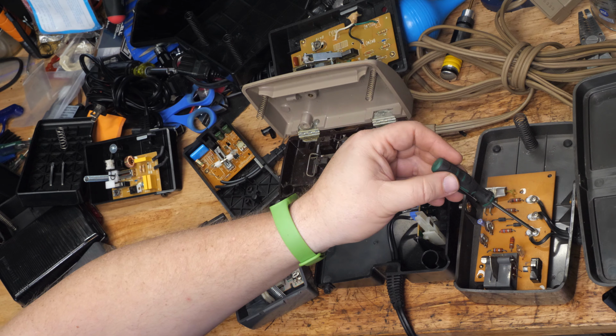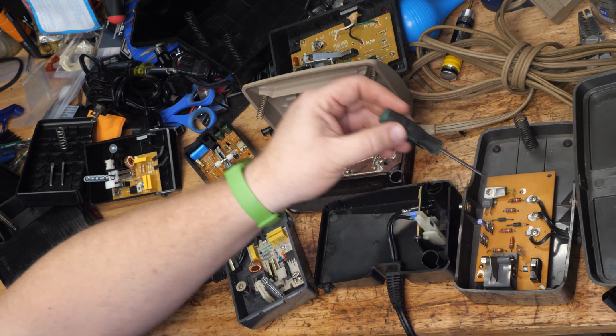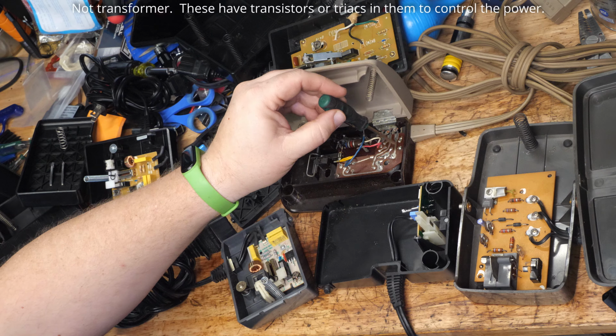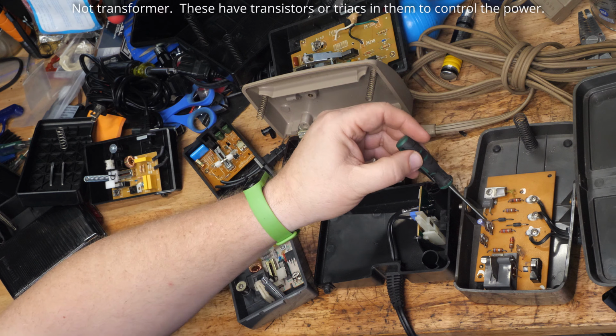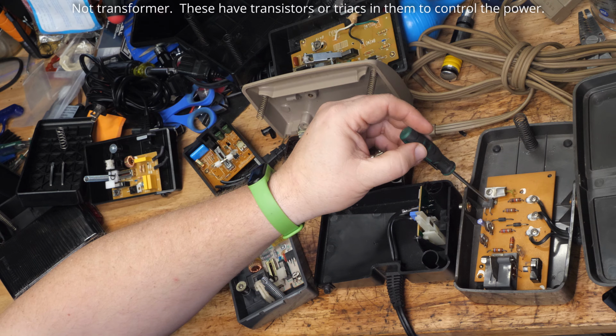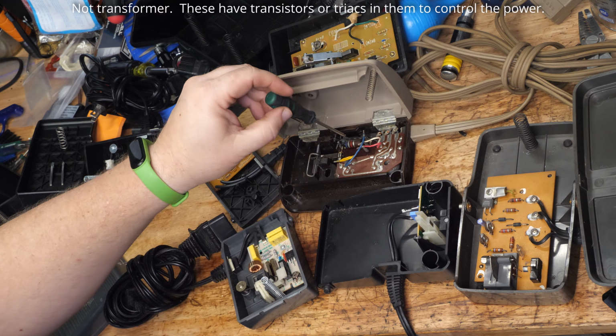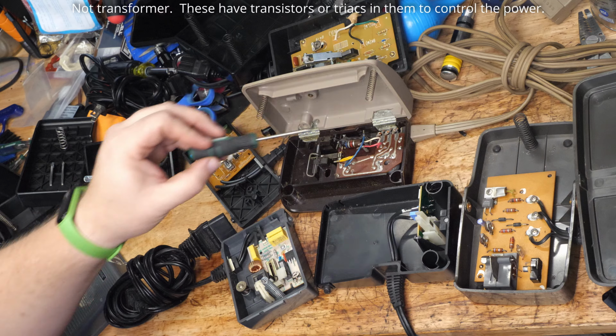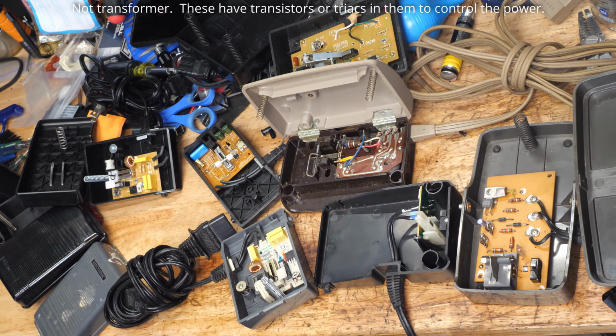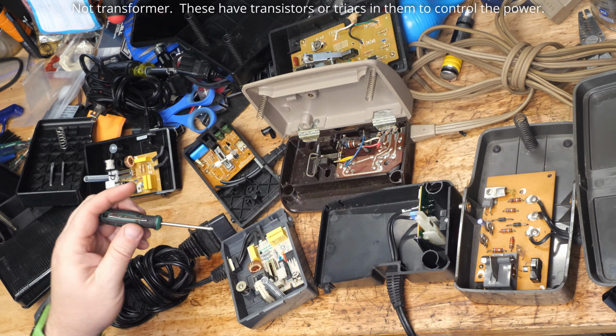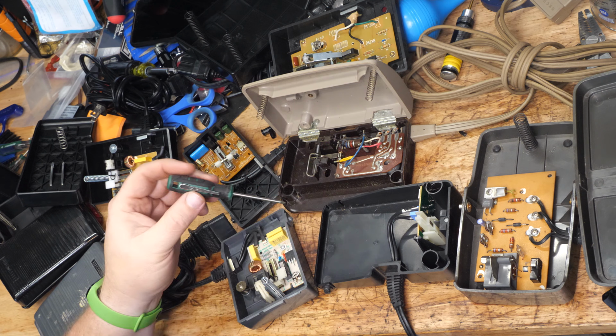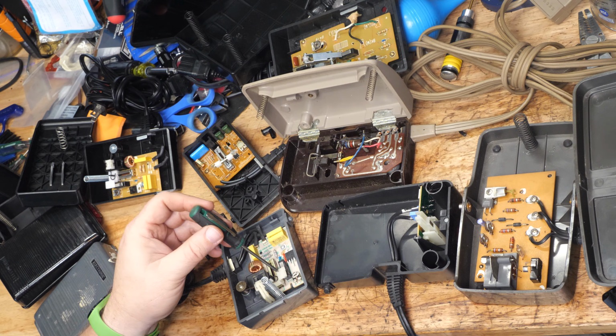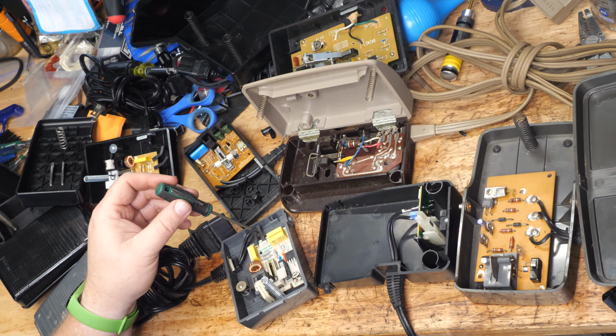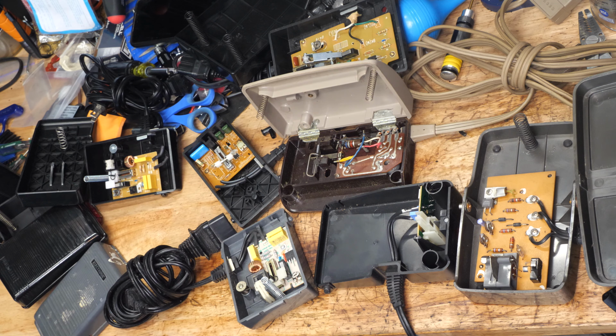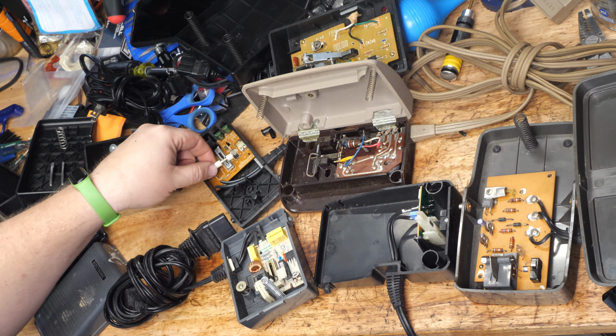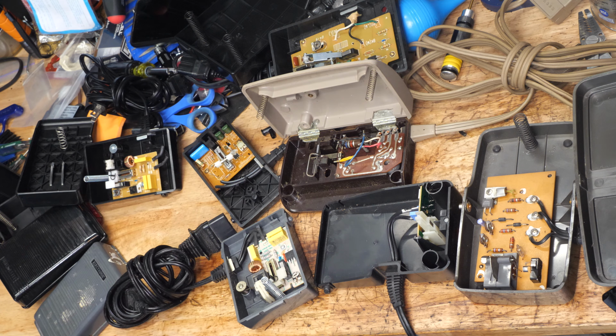So they always have full power in them, and then the motor lead comes off of the big transistor or triac or whatever part controls it. Newer controllers figured out a way to make the circuit work without needing to have power all the time. That's why newer controllers only have 2 leads.